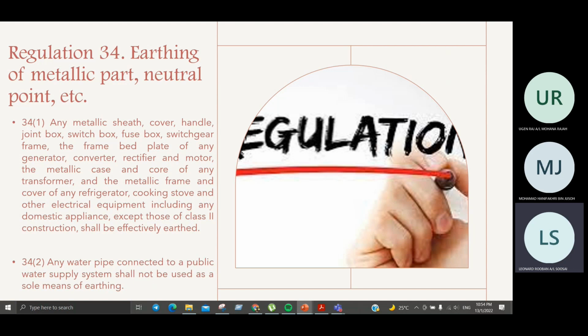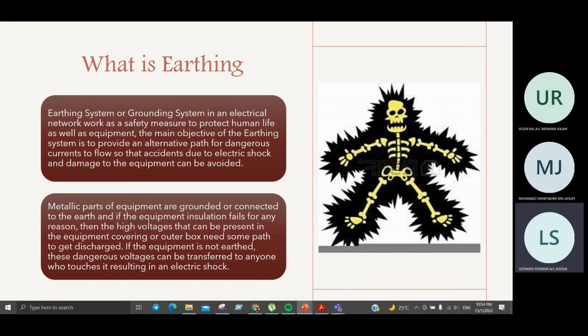So from this we can see that both situations are not earthed in the right way: the earthing for the metal clad and also the earthing to the water pipe. So from this we should know why it is wrong. So what is earthing? First of all, an earthing or grounding system is an electrical network working as a safety measure to protect human life as well as equipment. The main objective of this earthing system is to provide an alternative path for dangerous currents to flow, so that accidents due to electric shock and damage to the equipment can be avoided.